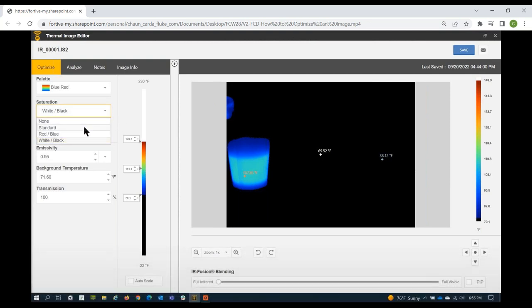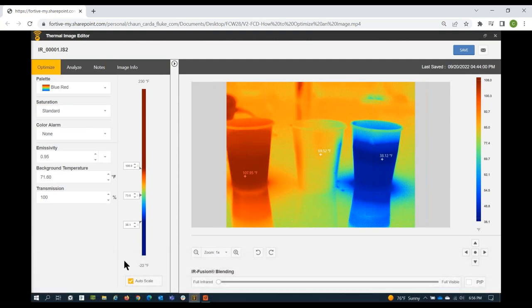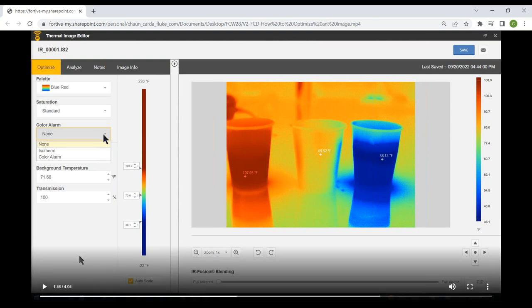We set it back to Standard and move on to Color Alarms. We have three options: None, Isotherm, and Color Alarm. Isotherm lets you illuminate a temperature range from within your span. With saturation we were looking outside of our span; now with isotherm we look at data within our span — between 108 and 38 degrees.